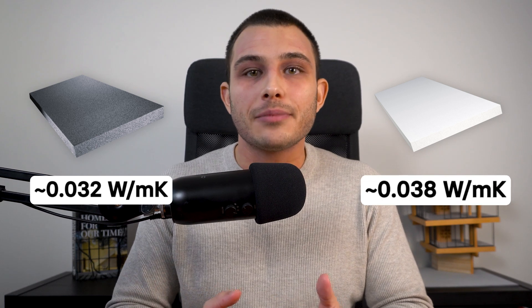For example, gray EPS contains graphite, which brings additional thermal properties and makes it more effective than white EPS. Gray EPS has a lambda of around 0.032 watts per meter Kelvin, achieving around 20 percent better insulation than white EPS, which has a lambda of around 0.038 watts per meter Kelvin.